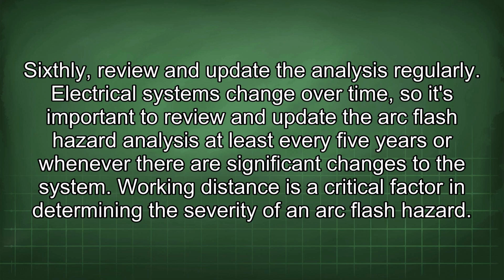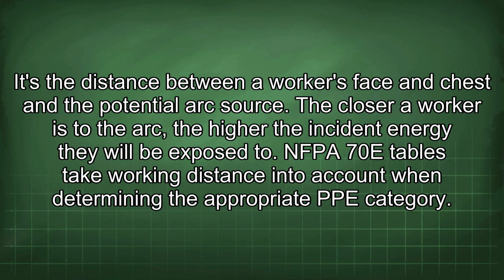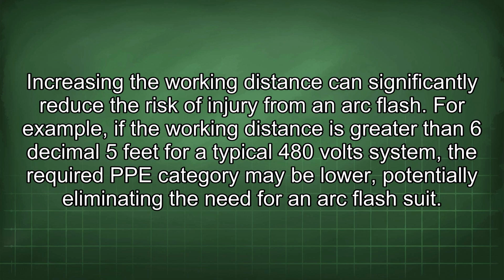Working distance is a critical factor in determining the severity of an arc flash hazard. It's the distance between a worker's face and chest and the potential arc source. The closer a worker is to the arc, the higher the incident energy they will be exposed to. NFPA 70E tables take working distance into account when determining the appropriate PPE category. Increasing the working distance can significantly reduce the risk of injury from an arc flash. For example, if the working distance is greater than 6.5 feet for a typical 480-volt system, the required PPE category may be lower, potentially eliminating the need for an arc flash suit.